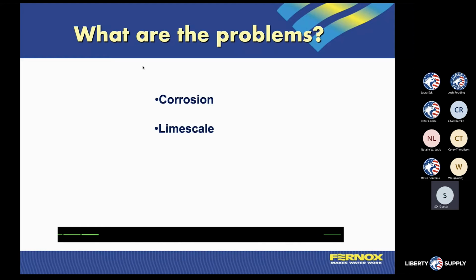From that can be from a pH level that's in the state of alkalinity or from the state of acidity. So we're going to be talking about those two different pieces of the puzzle. We're also going to be talking about limescale. Limescale is the mineral that's in most of the water that we run into in the Midwest here. As we drill our wells and get into the aquifer, sometimes an aquifer is surrounded by limescale, and that comes up with the water, and that's what is going to plate or stick to the inside of the heat exchanger.